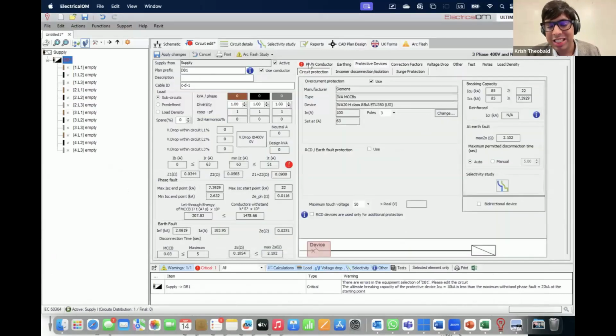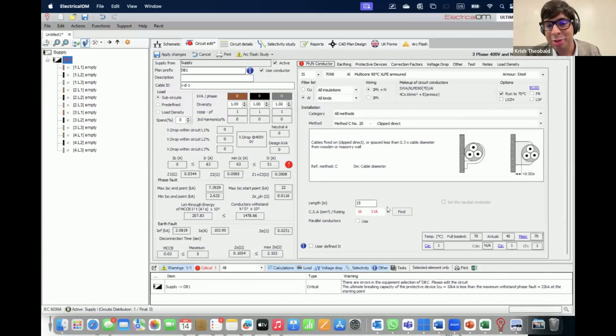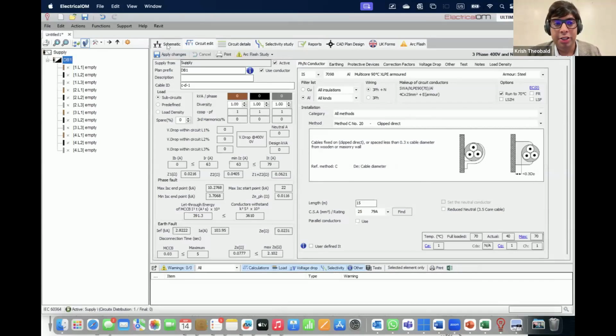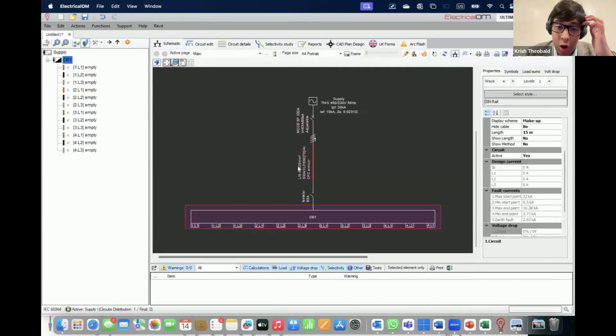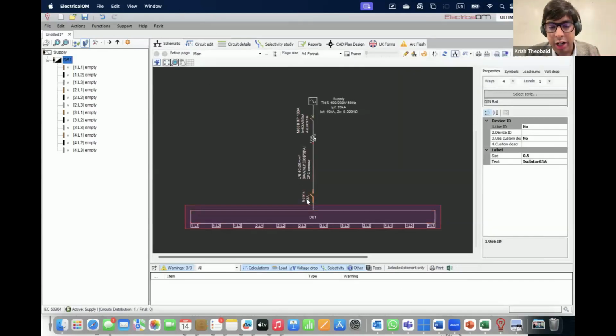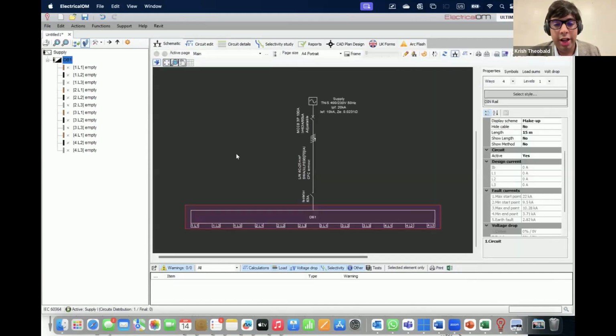Brilliant. Now, you see, it's giving me a warning that the 16 square mm is not enough because I need a minimum of 63, but in this arrangement, the 16 square mm can only carry 51. So that's where this comes into the picture. I can select a reduced 3.5 core as well if required. Now, if I save, see the warning disappears. Now I've got my cable, and now this is going to be an isolator here as well, and that's fine.